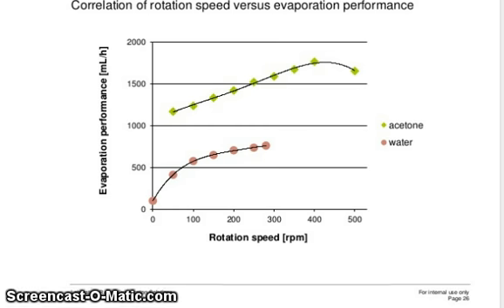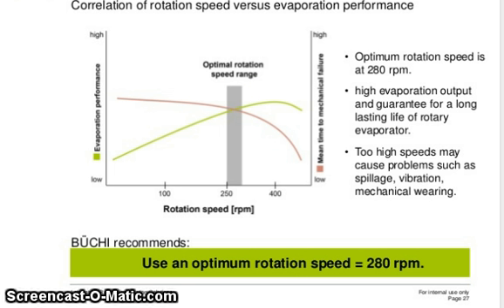Correlation of rotation speed versus evaporation performance — evaporation performance in milliliters per hour versus rotation speed, shown for acetone and water. The optimum rotation speed is at 280 RPM, giving high evaporation output and guaranteeing a long-lasting life of the rotary evaporator. Too high a speed may cause problems such as spillage, vibrations, and mechanical bearing wear. Use the optimum rotation speed of 280 RPM.